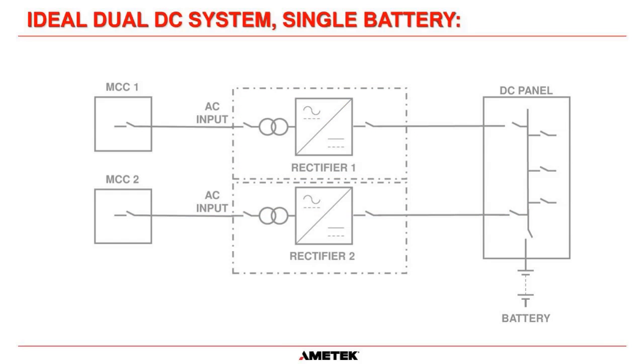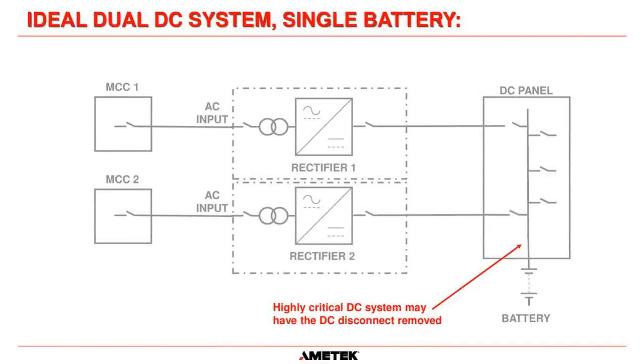The only issue that we have on this system here is we only have 1 battery. So if we do have a fault on this battery here and we need to replace it, then what we would have to do is open this breaker here, and that means we wouldn't have any battery backup when we were performing either the maintenance or the replacement. So this is nearly the best way to design your DC systems, but not quite there.